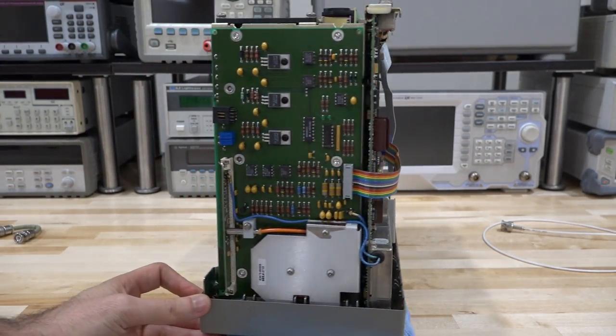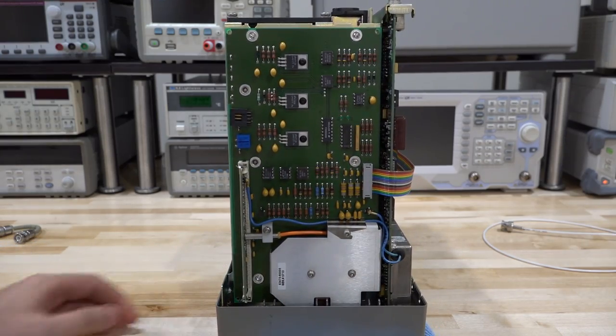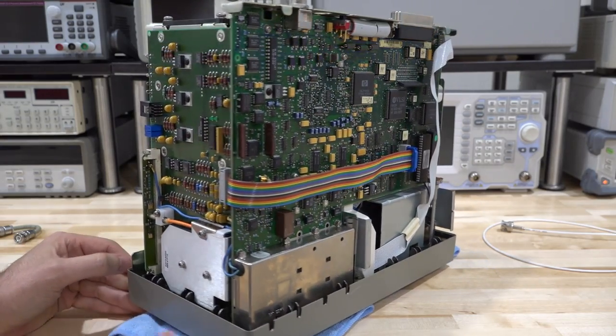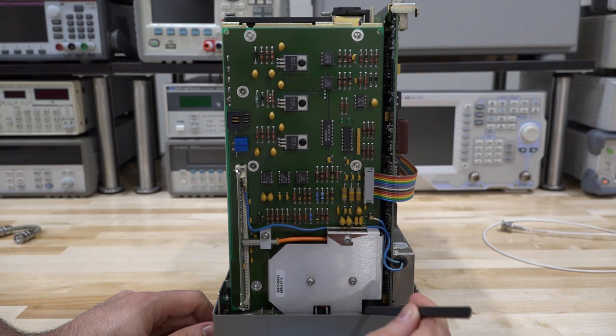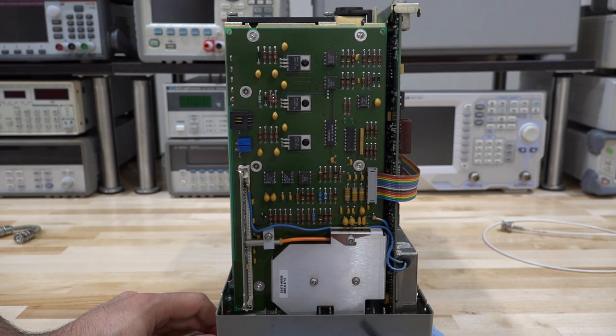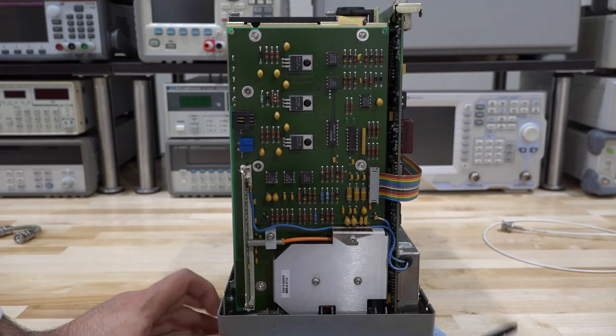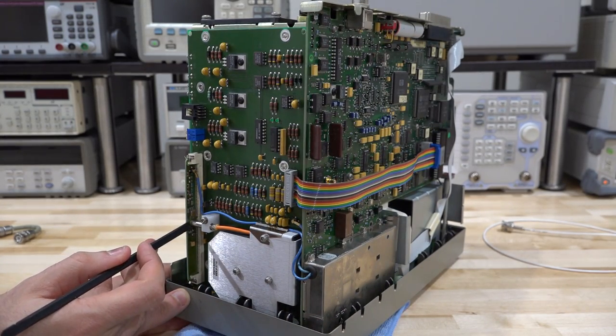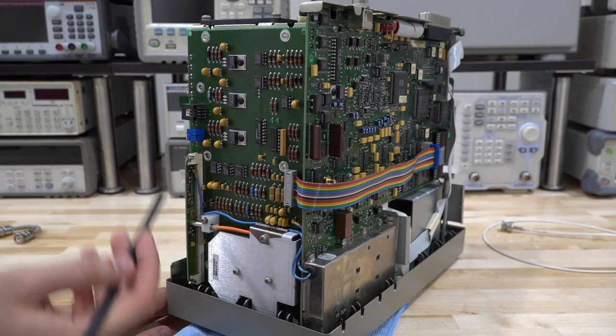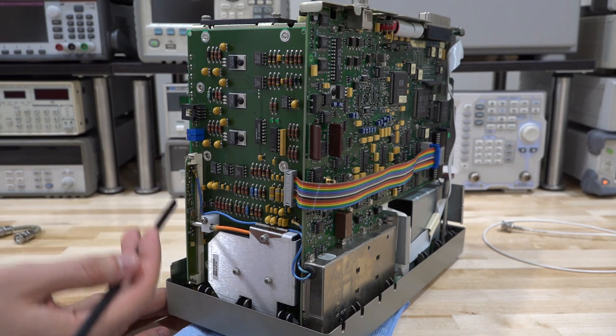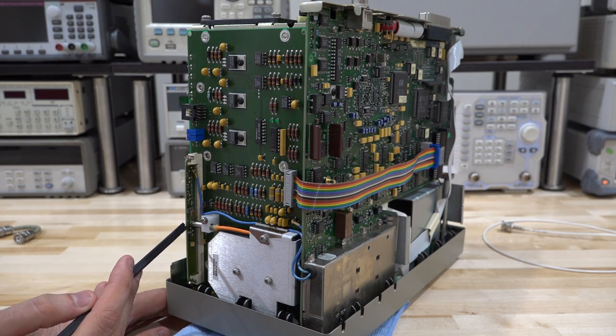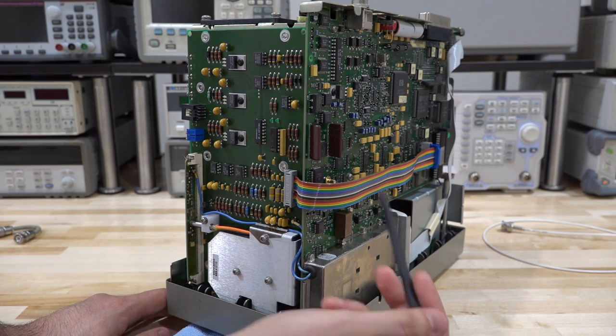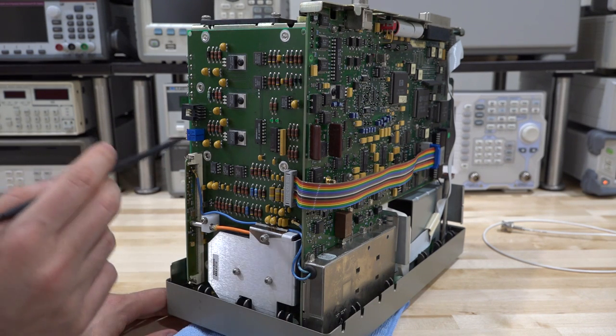Let me plug this back so we can rotate this a little bit again. This is pretty interesting. Check this out. This is our optical portion. Let me rotate this to see where this fiber is coming from. There it is. So right over here, where you cannot see where the tip of this is, is the optical input. And that fiber goes over here. And this is that orange fiber over here. And it looks like it goes into a collimator. And then into a photo detector right there. So this card actually is something that can be plugged out and plugged back in for modifying perhaps the wavelength sensitivity or calibrating these ahead of time. But it's an interesting design that the fiber comes in and then just directly onto this detector there.